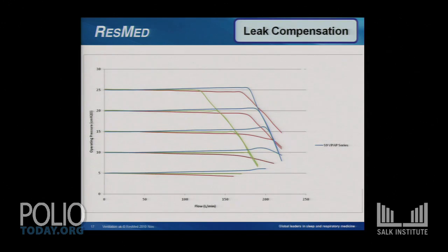Now this shows you our wonderful S9 VPAP series in the blue. And some competitive products are in the green and the red. And you might think, what the heck am I looking at here? Well, here we can see the flow rate along the bottom. And along the side here is the mask pressure. So here we have a pressure of 20. Here we have a pressure of 25. So that's a really high pressure. So let's take a look at that. In this particular example, the S9, the ResMed product, was able to come to a flow of, I don't know, what is that, about 180 liters a minute before the pressure dropped off.